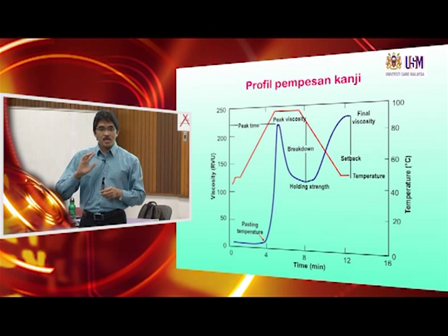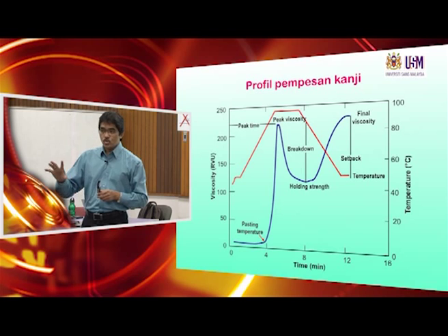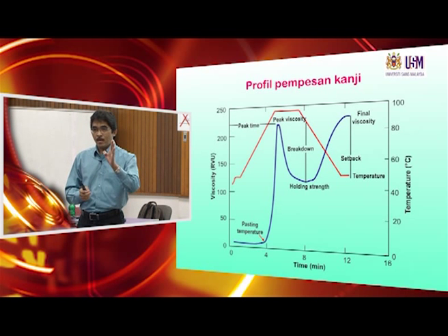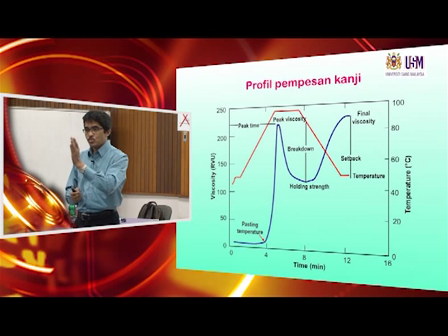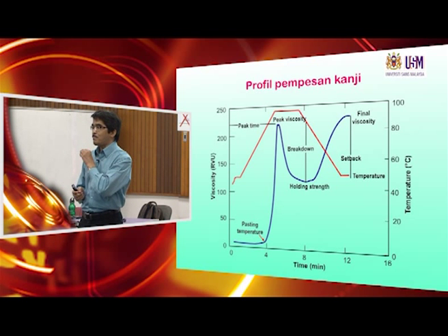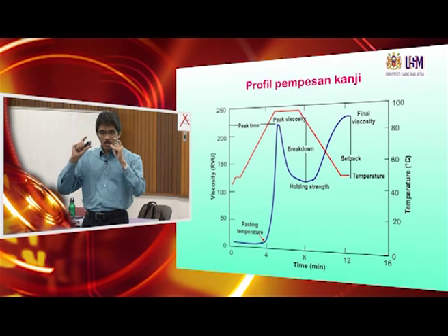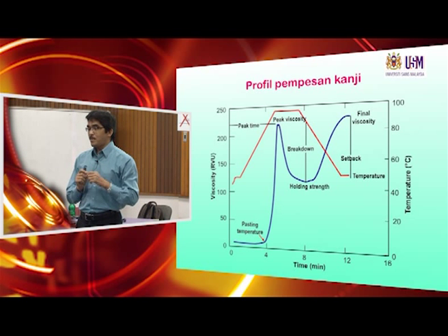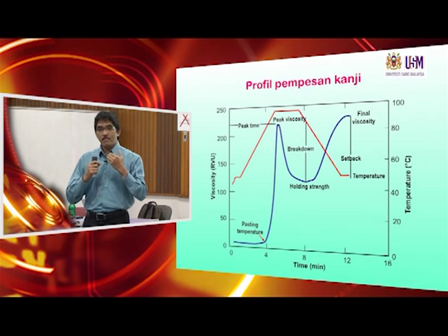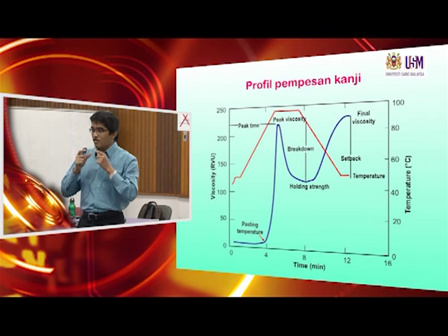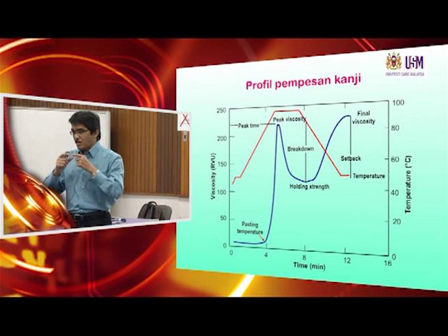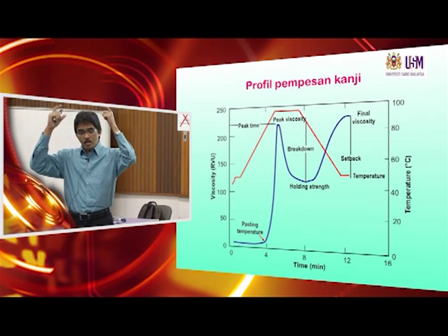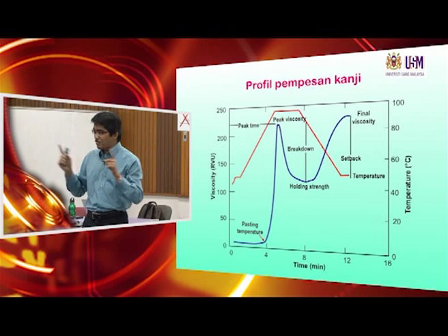But if you apply a standard heating program, as in the rapid visco analyzer, if you have used it, there's a standard program, program 1, program 2. Usually in the rapid visco analyzer, the standard holding time may be a few minutes. But then we can change that, depending on what kind of information you want in terms of the stability of the starch, the ability of the starch to hold the viscosity at 95 degrees Celsius. So it can be longer.